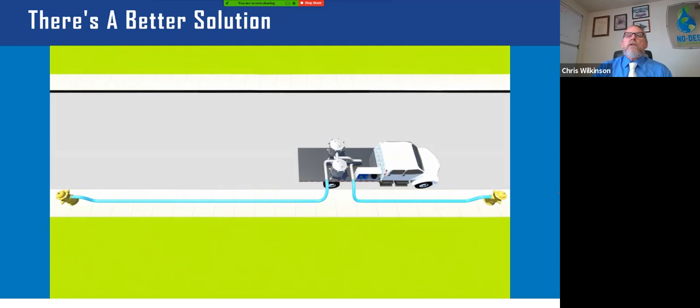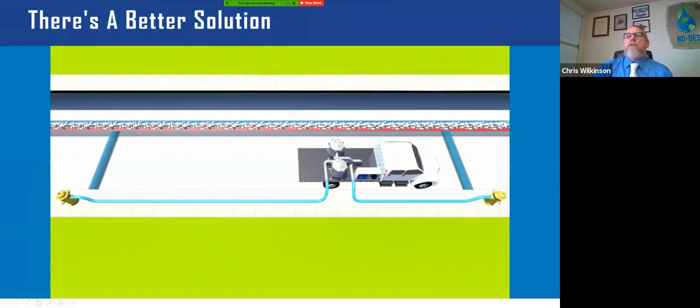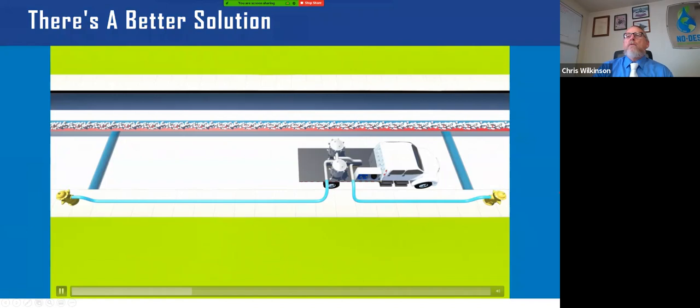In the street, the general flow of water is going from the right of your screen over to the left-hand side. That's just the flow that everybody's getting served with. We use these little bubbles just so you can actually see it. The dirt or buildup of biofilm, magnesium, iron, things like that, is represented by the red. So everything's flowing. We have the hydrants open. The hoses are energized. Everything's pressurized. We're ready to go. So what we're going to do now is turn the NODES system on.